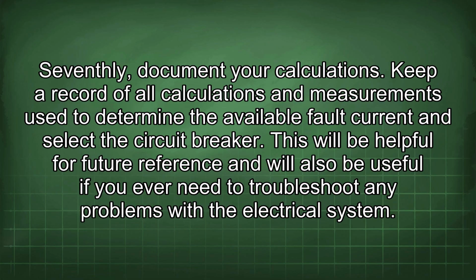Seventhly, document your calculations. Keep a record of all calculations and measurements used to determine the available fault current and select the circuit breaker. This will be helpful for future reference and will also be useful if you ever need to troubleshoot any problems with the electrical system.